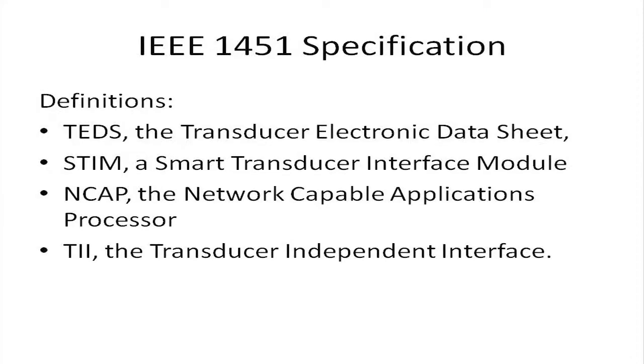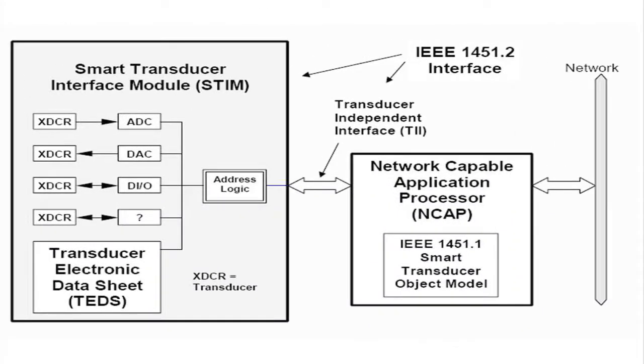However, if you want plug-and-play functionality from a network of sensors, IEEE specifically developed 1451 standards for smart sensors. Several terms were defined to make plug-and-play sensing possible. The terms include the TEDS — the Transducer Electronic Data Sheet — a smart transducer interface module, NCAP — the Network Capable Applications Processor — and the TII, the Transducer Independent Interface.